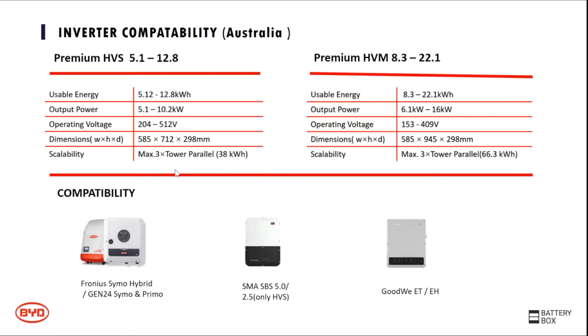This is highly recommended for you to look at if you're not familiar, because the battery is a modular design. There are quite a few options, like combos together with different inverters. Some combos are not compatible due to technical issues. So in this inverter list, and also the minimum configuration list - we call this one - there's very clear information on which combo is compatible and which is not. This is highly recommended for you to check and select the right models. Otherwise, if you use models that are not compatible with some inverters, unfortunately there's no warranty. So this is very, very important for you.